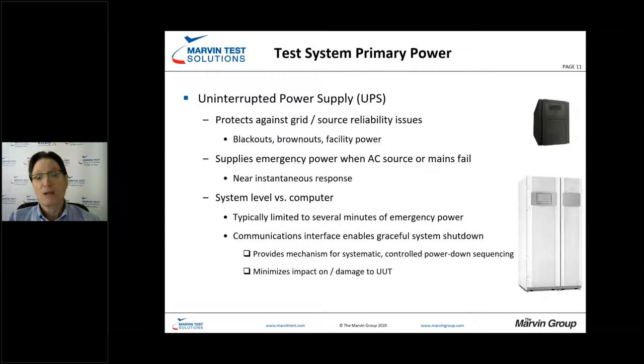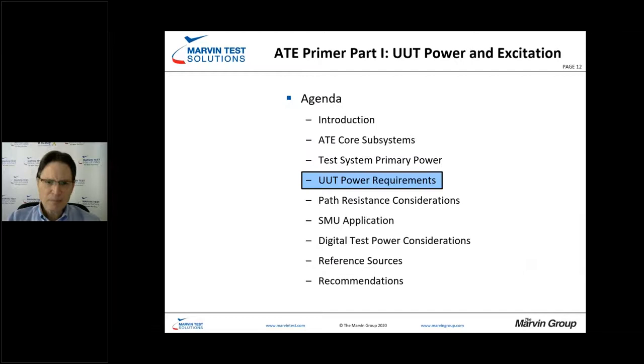Most modern UPSs provide a communications output that allows us to monitor power status. Once we get a trigger that we've had a power fault, we can gracefully shut down the UUT, pull our stimulus off, pull the rails off, and then gracefully shut down the test system. The UPS isn't meant to run tests for three more hours — it's to protect the test system, protect the UUT, and gracefully power down.